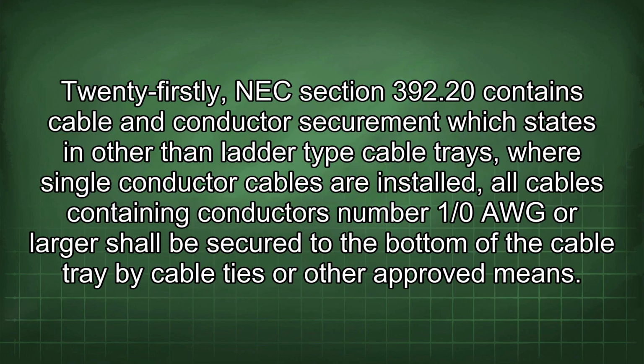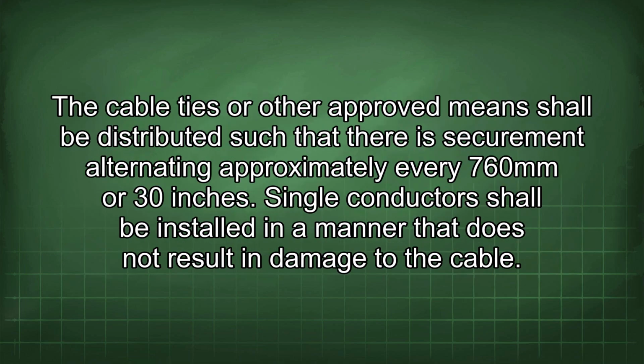21stly, NEC section 392.20 contains cable and conductor securement, which states in other than ladder type cable trays, where single conductor cables are installed, all cables containing conductors number 1/0 AWG or larger shall be secured to the bottom of the cable tray by cable ties or other approved means. The cable ties or other approved means shall be distributed such that there is securement alternating approximately every 760 mm or 30 inches. Single conductors shall be installed in a manner that does not result in damage to the cable.